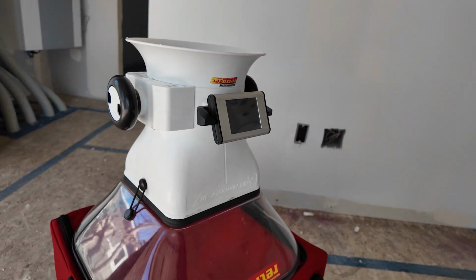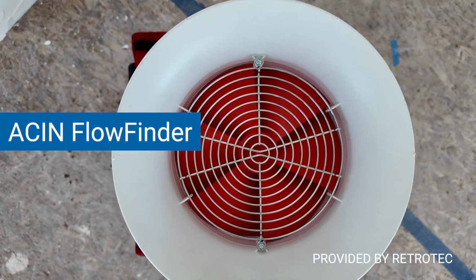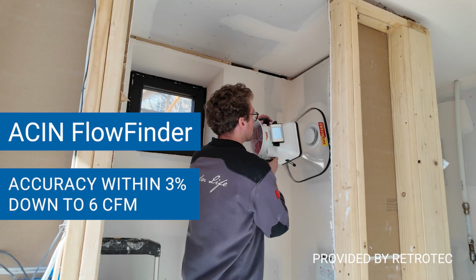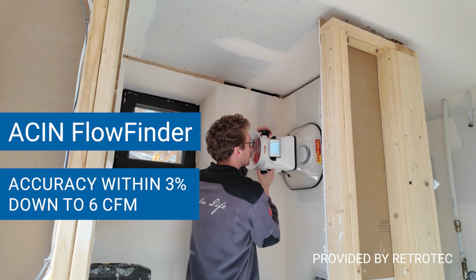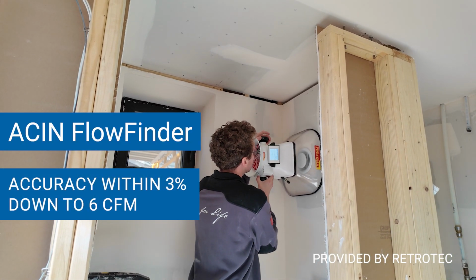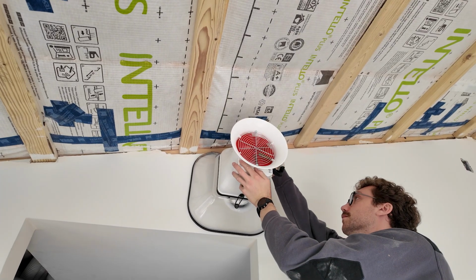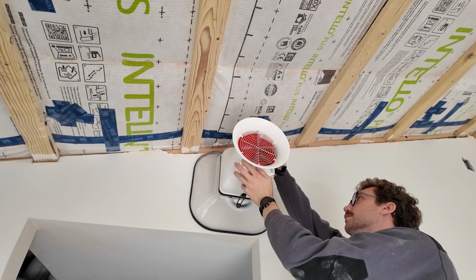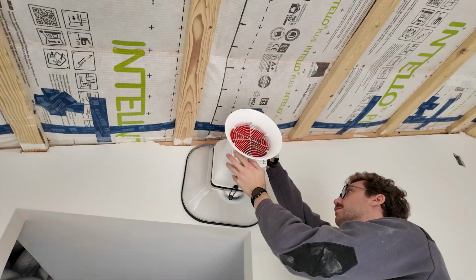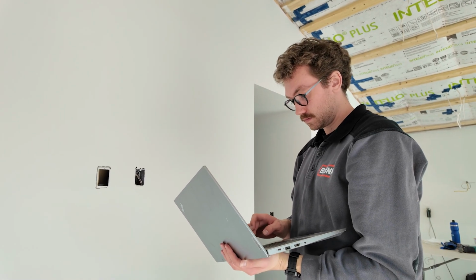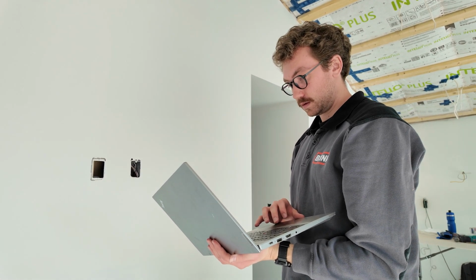At 475, we've found success with the ACIN FlowFinder because it has an accuracy within 3% down to 6 CFM, and it mitigates the effects of back pressure. This is among the most accurate flow hoods on the market, which is essential for measuring the continuous but low flows of an ERV or HRV system.